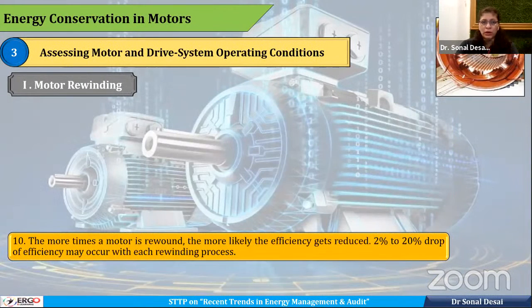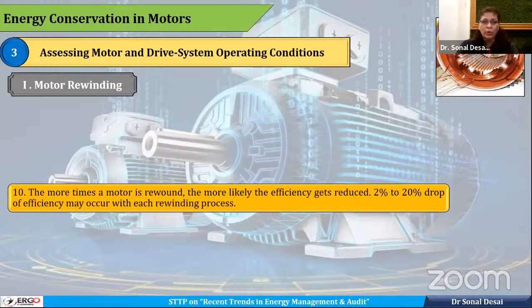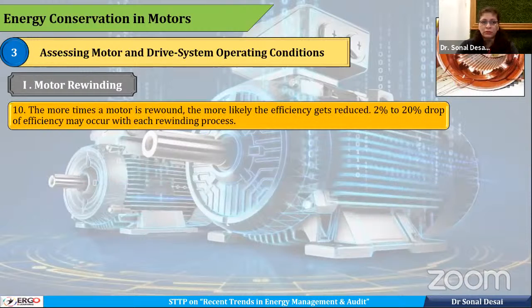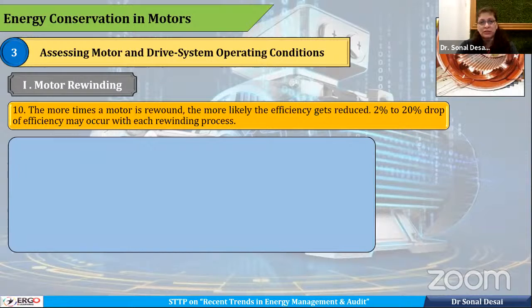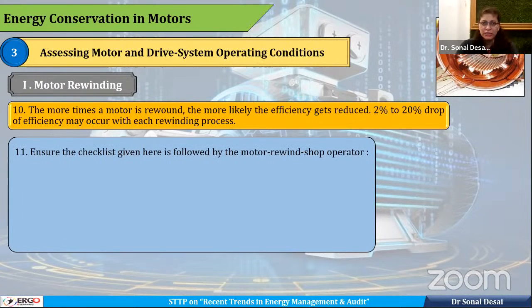Then some more guidelines for rewinding. Whenever a motor gets rewound again and again, every time its efficiency drops in the range of 2 to 20%. So when you are having a second or third rewinding, it will have a drastic reduction in the efficiency. So this is a checklist to consider when we rewind the motor.